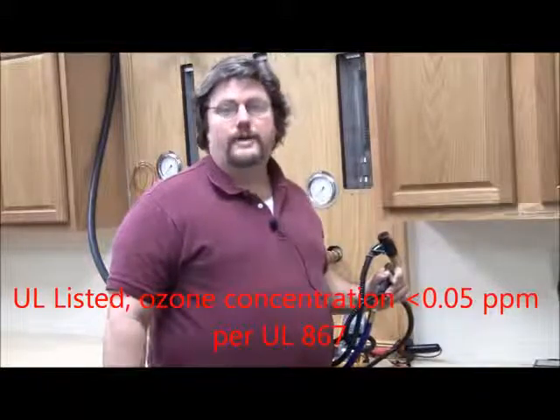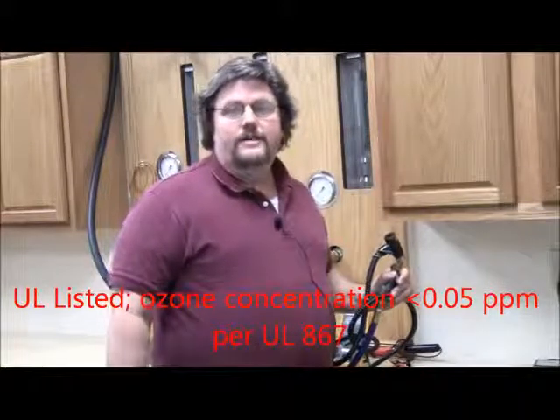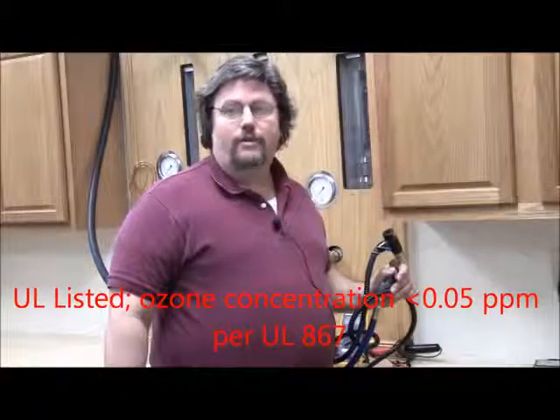How do you know if a static eliminator is operating properly? There are a couple of ways to check this. Let's start with an easy one. With the compressed air turned off and the power supply turned on, you can sniff around the outlet of the device for the presence of ozone. This is the oxygen ion produced by the high voltage of the emitter point. There's no need for concern. It's a very low current and shockless, less than 40 microamps short-circuited. Ozone has a very distinct odor, often described as sweet, pungent, or metallic. This is a very simple and easy way to perform a qualitative test.